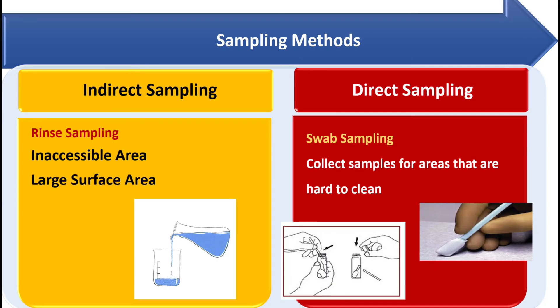There are two types of sampling methods: indirect sampling, also called rinse sampling, and direct sampling, also called swab sampling. In swab sampling, a small area of cleaned equipment is swabbed, the swab is extracted and added to a diluting solvent, and then the extract is examined by a suitable analytical method. In rinse sampling, residue is collected from the overall equipment — not restricted to any particular location. Equipment is cleaned by several washing cycles using water for injection or purified water, and then the rinse sample is analyzed.